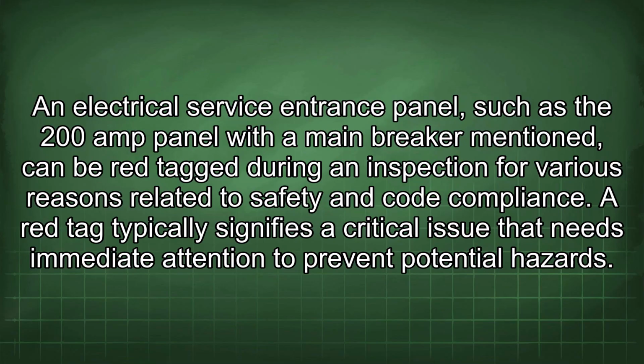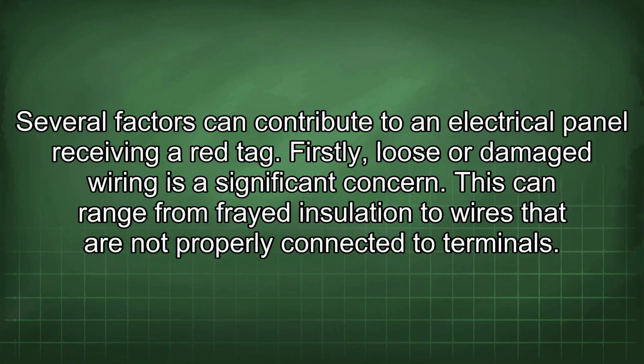An electrical service entrance panel, such as the 200-amp panel with the main breaker mentioned, can be red tagged during an inspection for various reasons related to safety and code compliance. A red tag typically signifies a critical issue that needs immediate attention to prevent potential hazards. Several factors can contribute to an electrical panel receiving a red tag.